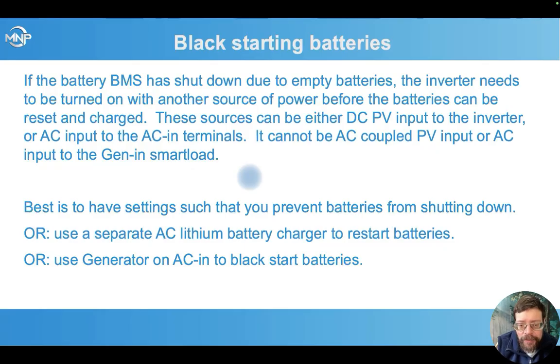One way is to have a separate lithium battery charger that runs off of AC that can restart the batteries. It's about $100 to $150 for a 15 or 20 amp 48 volt lithium battery charger that you could wire in such that if you need to, you can run generator power into that and bring those batteries up enough to turn the battery BMS back on, then turn the inverter back on, and then start charging through the normal generator port.